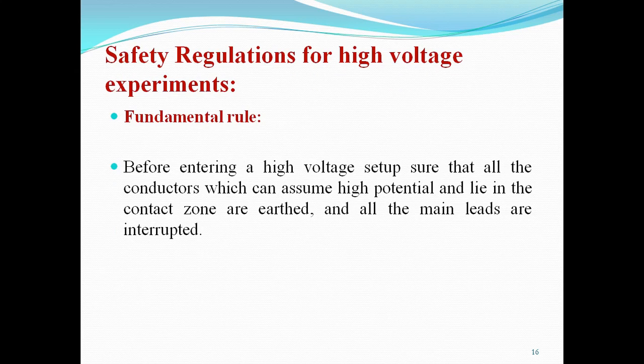Safety regulations for high voltage experiments. When you are going to perform the test in the laboratory, you have to remember certain rules. The fundamental rule: before entering a high voltage setup, make sure that all the conductors which can assume high potential and lie in the contact zone are earthed and all the main leads are interrupted. Whenever you enter the laboratory, you have to see that your equipment is not connected with the main supply, and you have to discharge all the equipment with the help of the earthing rod.